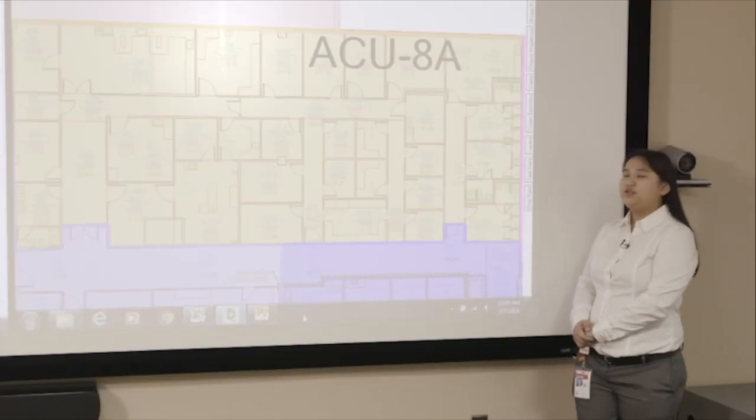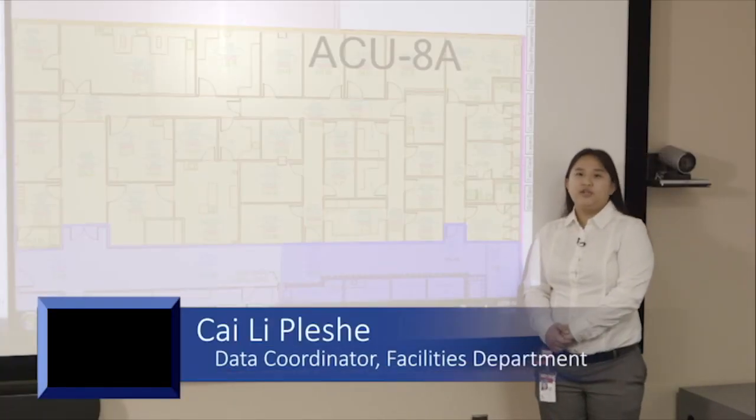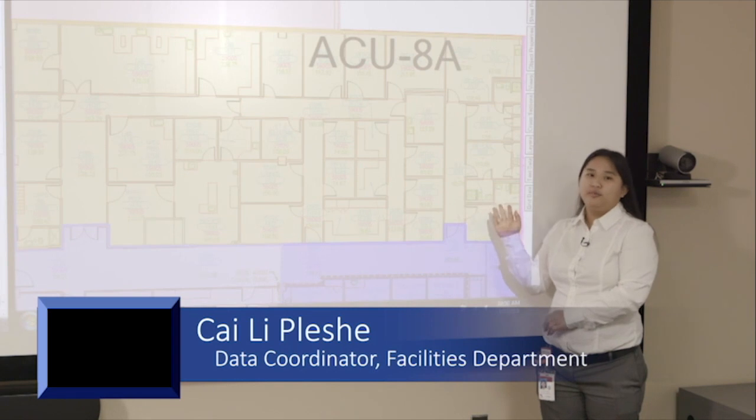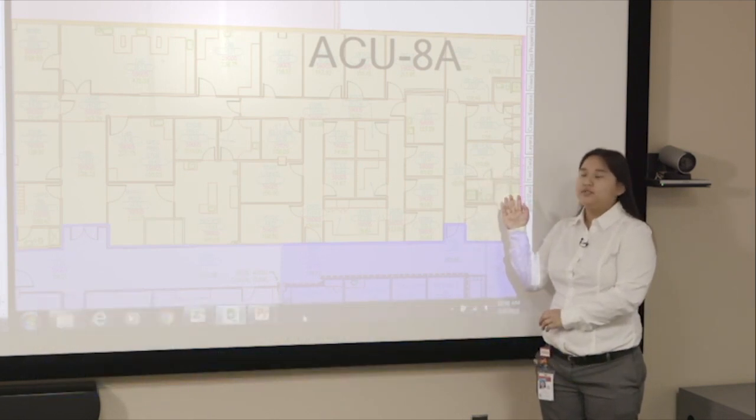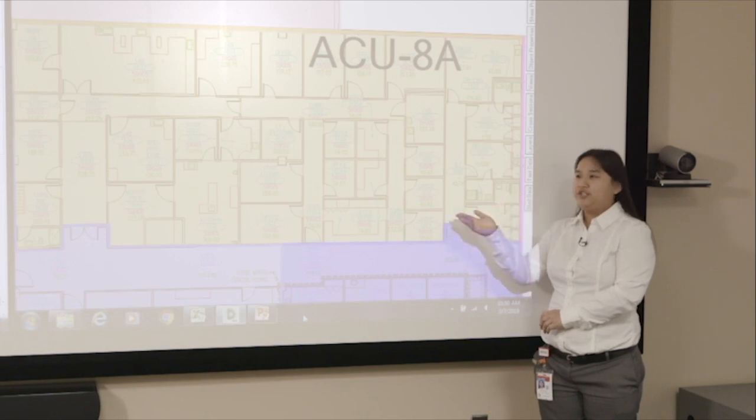So could you give me a little bit more on what I'm looking at here and explain how you came up with the category of risk? So we took our mechanical drawings and our life safety documents and we put it on a floor plan, and it lays out what air handler touches what specific rooms. And then from there we put it on a spreadsheet.